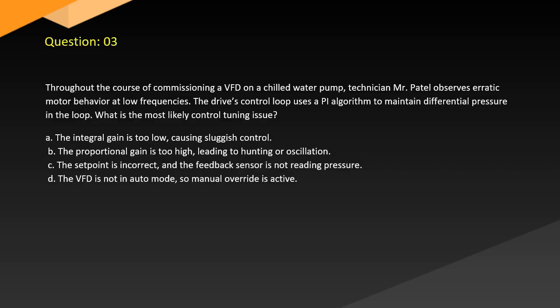Question 3. Throughout the course of commissioning, a chilled water pump technician, Mr. Patel, observes erratic motor behavior at low frequencies. The drive's control loop uses a PI algorithm to maintain differential pressure in the loop. What is the most likely control tuning issue?